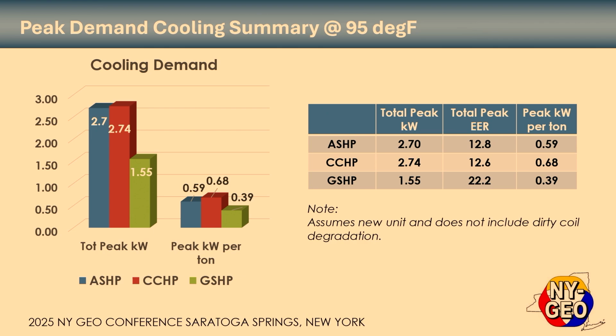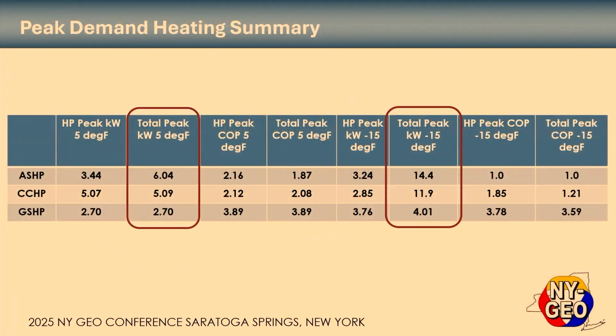Yeah, hi, I'm Hugh Henderson at Owegina Consulting. Good job, Bob, of walking through all this. So the air or cold climate heat pump compared to geothermal comparison, you're seeing that the geothermal demand is about 3 times lower, right? That was kind of your summary for heating. I understand all that and understand your calcs. So I can tell you from field testing of air source heat pumps, we've seen that ratio be maybe closer to 2. And I think it's because there's diversity in loads.